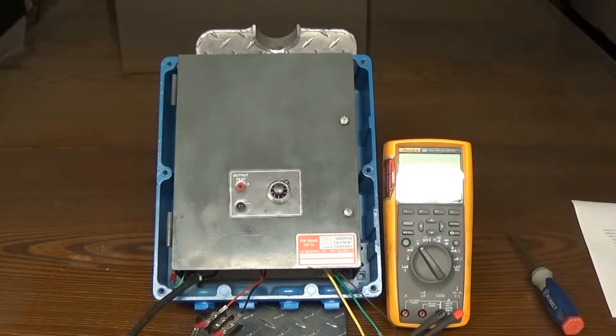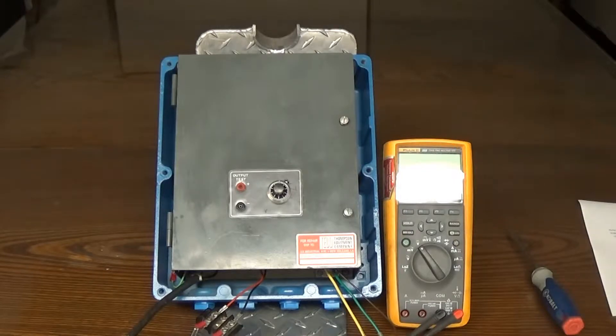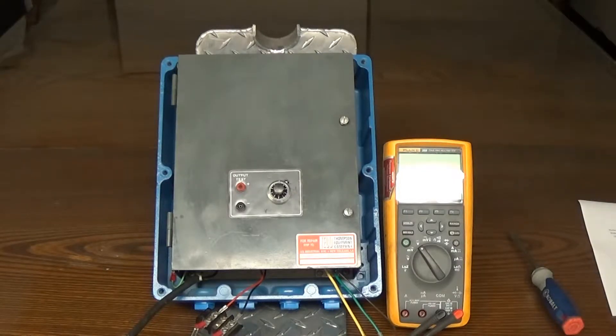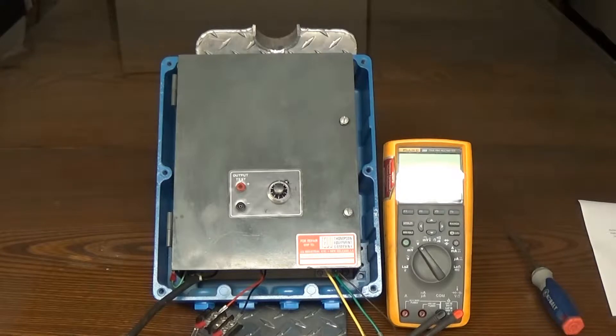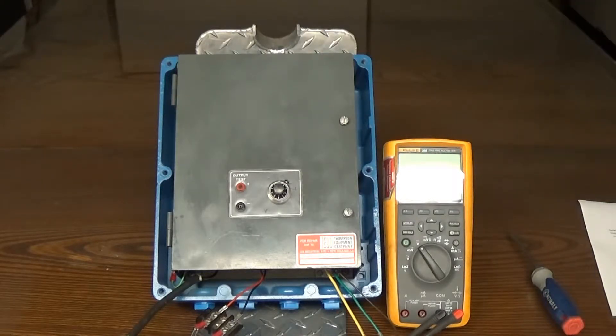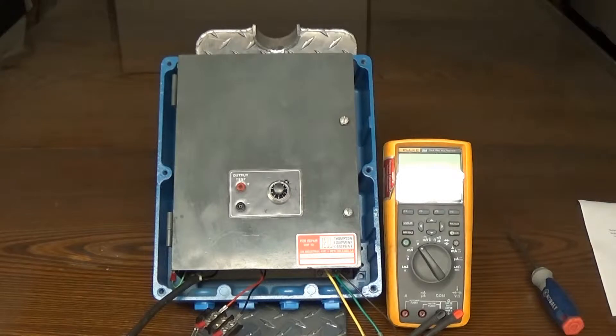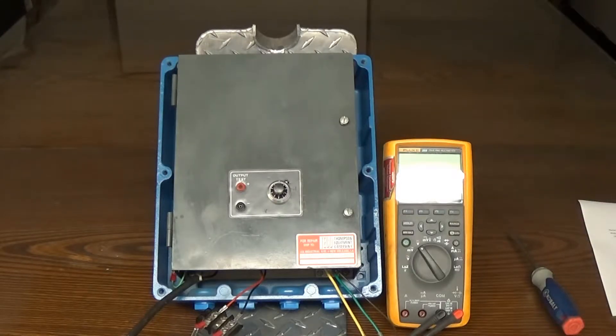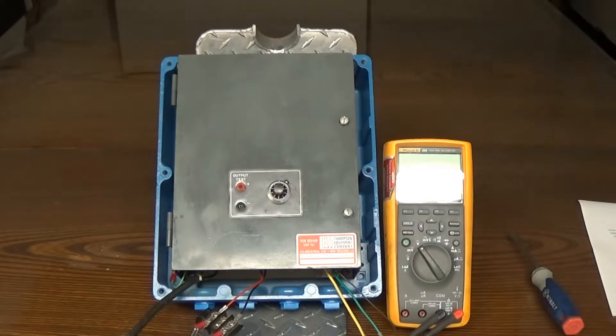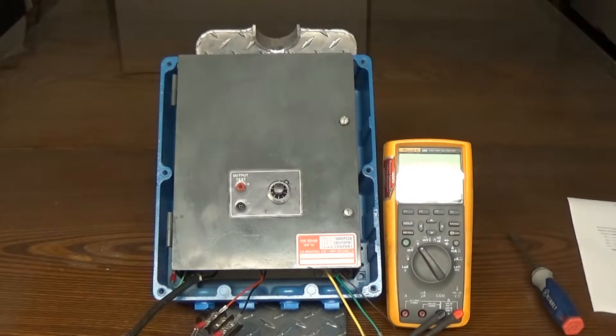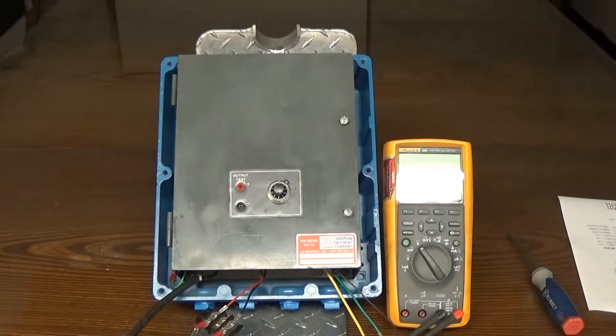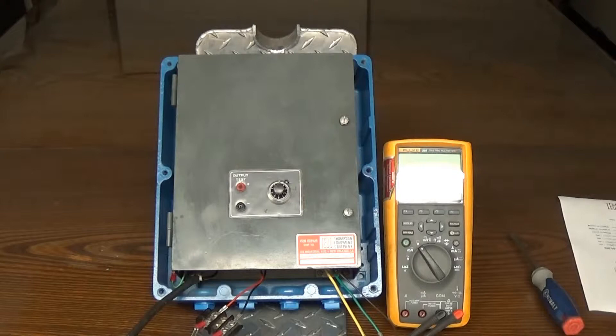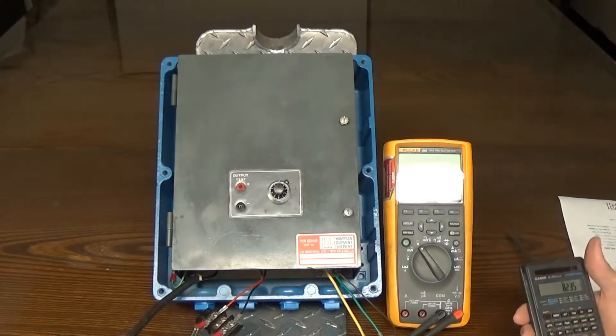You will receive a calibration sheet with a calibration factor. Even though it doesn't state on the sheet what units it's in, it's millivolts per GPM. You will have to know this number and multiply it times your intended upper range value on your process. We're going to be using 250 gallons per minute as an intended range value here. The calibration factor that I have from this sheet is 0.03294 millivolts per GPM.